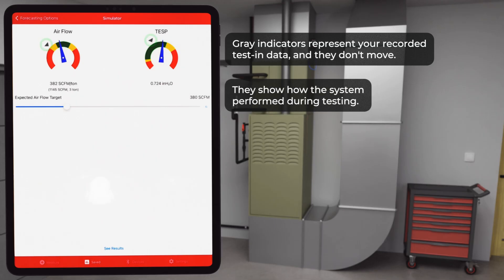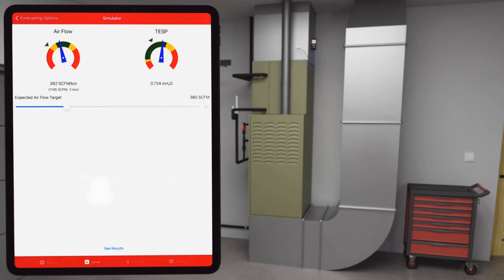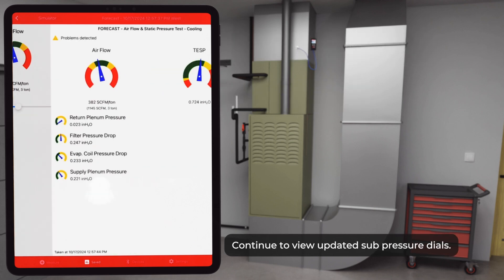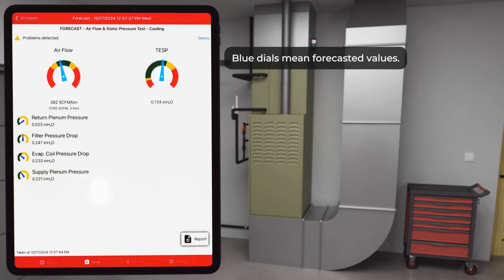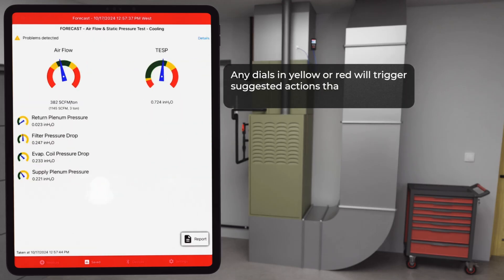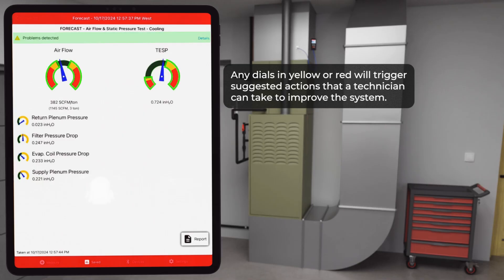A helpful visual to compare where the system started. Once you set your new airflow rate, tap continue to view updated sub-pressure dials. These include return, filter, coil, and supply pressure drops. Again, blue dials mean forecasted values and gray triangles show your test end values. Any dials in yellow or red will trigger suggested actions that a technician can take to improve the system.